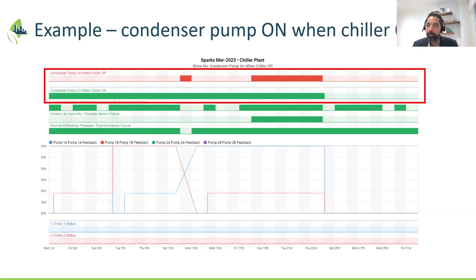Another rule: the condenser pumps were running when the chiller was off. A simple fix is to talk to the operator, turn them off, and you get all the savings from that pump.